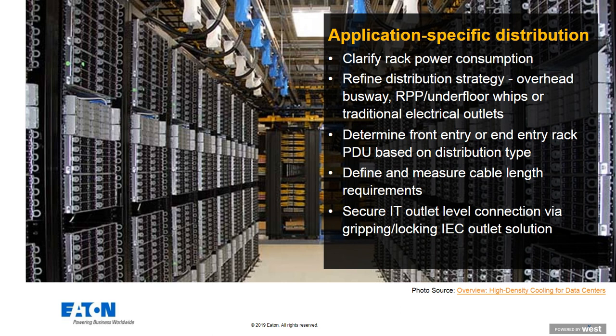So that brings you to the decision on a PDU of how does the PDU sit in the rack? Does it sit with the cable coming out the top, the cable coming out the bottom? And do you want the power cord coming out the face of the PDU or the end of the PDU? That comes into physical constraints within the rack enclosure and how that PDU best fits into the rack. And then the next thing you want to look at is cable length.